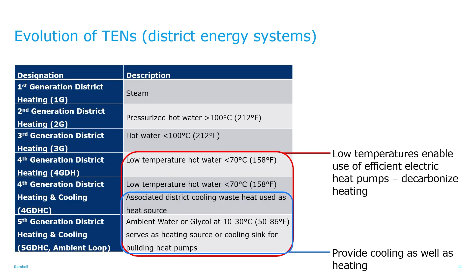Here's some typical characteristics of fourth and fifth generation thermal energy networks. Primary concept I covered in the previous slide. So the number of pipes, if it's heating only, 4G, they would have 2 pipes, otherwise would have 4 for the cooling as well. They're often insulated steel or insulated high temperature polymer sometimes now for heating, and insulated polymer for cooling. 5G systems come in 1 or 2 pipe varieties, and they typically have uninsulated polymer pipes.